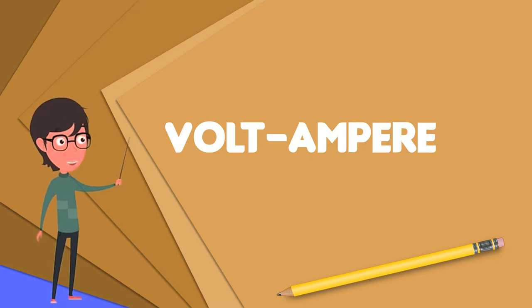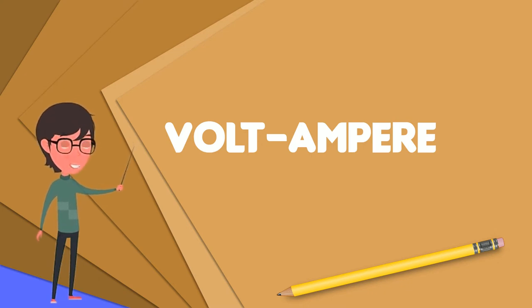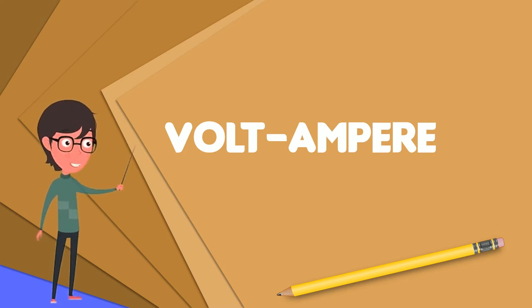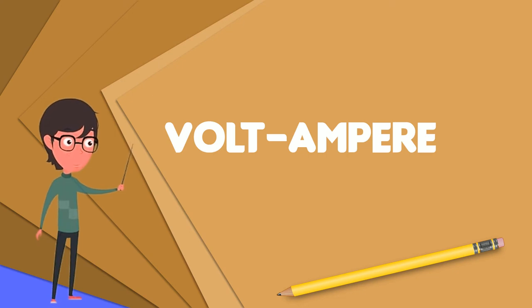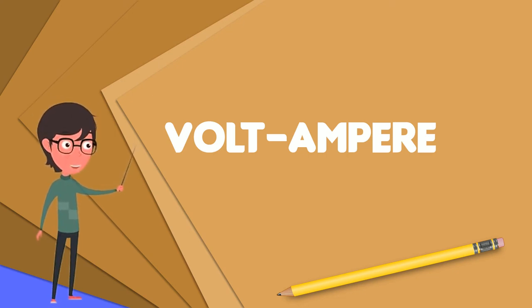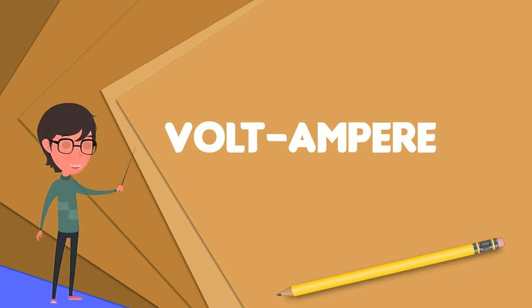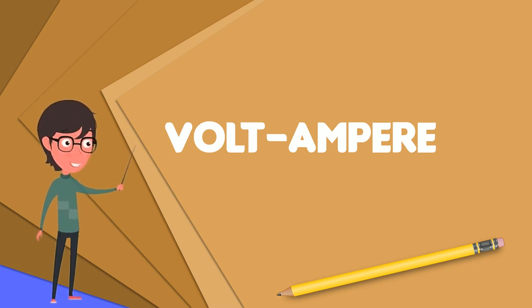When a UPS powers equipment which presents a reactive load with a low power factor, neither limit may safely be exceeded. For example, a UPS system rated to deliver 400,000 volt-amperes at 220 volts can deliver a current of 1,818 amperes.